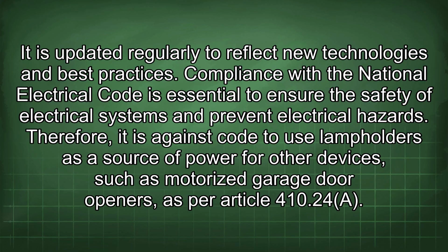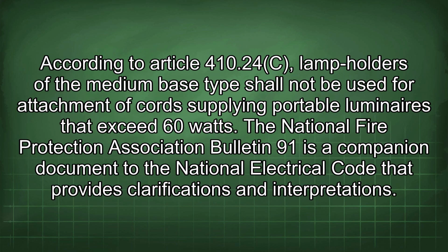Compliance with the National Electrical Code is essential to ensure the safety of electrical systems and prevent electrical hazards. Therefore, it is against code to use lampholders as a source of power for other devices, such as motorized garage door openers, as per Article 410.24(A).